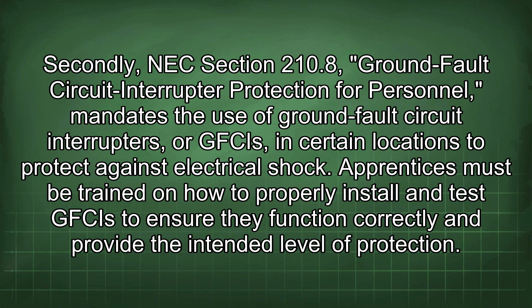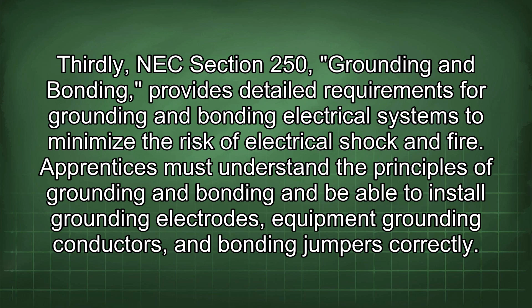Thirdly, NEC Section 250, Grounding and Bonding, provides detailed requirements for grounding and bonding electrical systems to minimize the risk of electrical shock and fire. Apprentices must understand the principles of grounding and bonding and be able to install grounding electrodes, equipment grounding conductors, and bonding jumpers correctly. Fourthly, NEC Section 300.4, Protection against physical damage, requires that wiring methods be protected from physical damage during and after installation. Apprentices must be trained on how to properly support and protect cables and conductors to prevent damage from impact, abrasion, or other hazards.